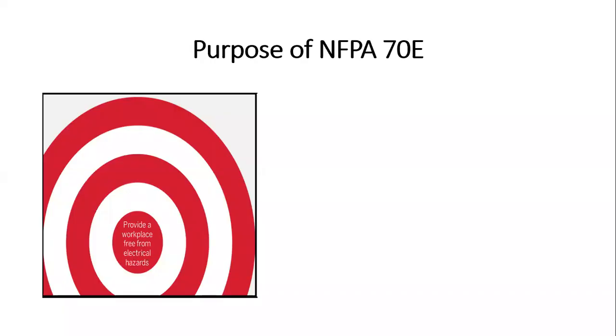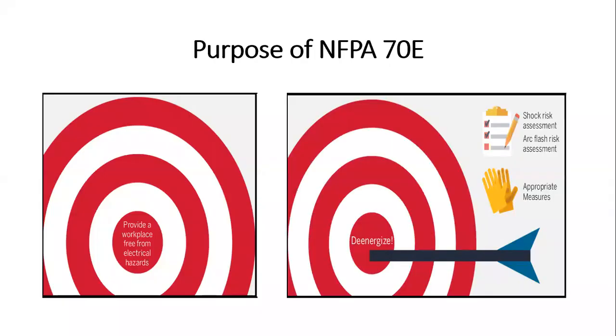So what's the purpose of NFPA 70E? The main purpose is to provide a workplace free from electrical hazards, and the second option is to do the work while the equipment is de-energized. Conduct the shock risk assessment, arc risk assessment, and take appropriate measures to safeguard yourself and your team from electrical hazard.